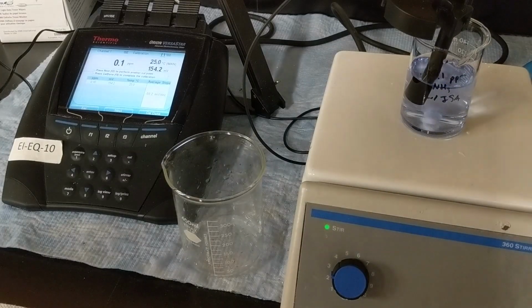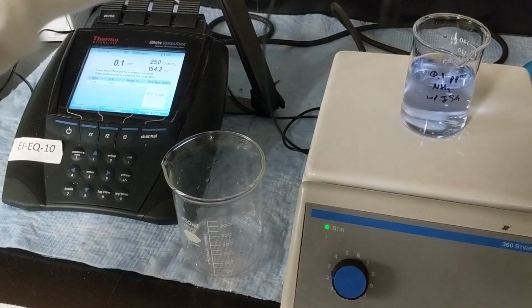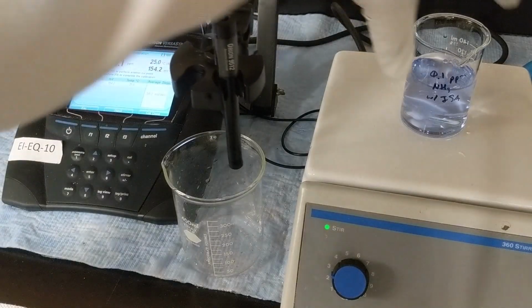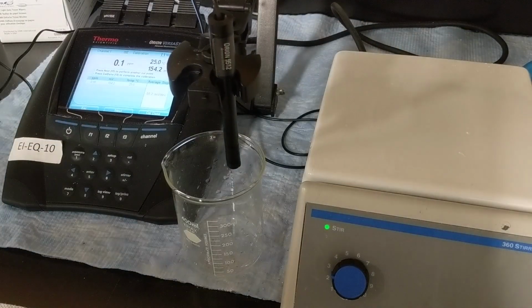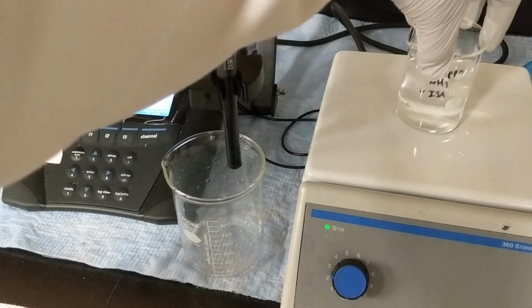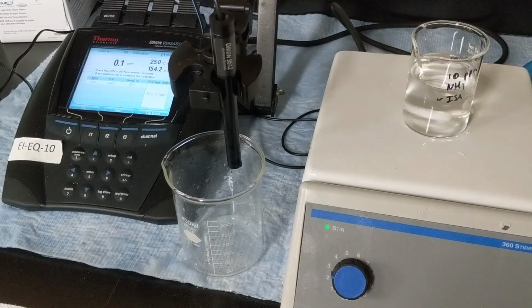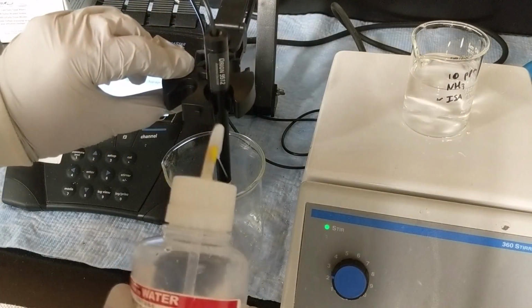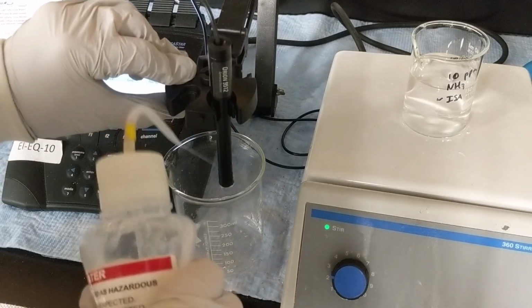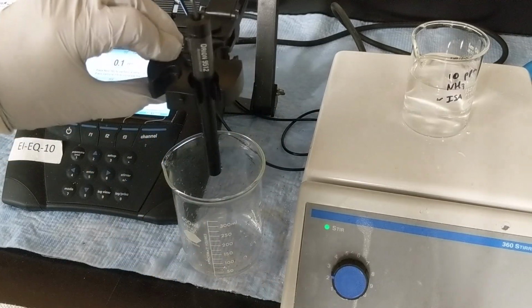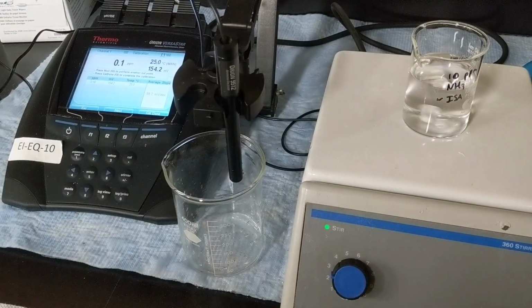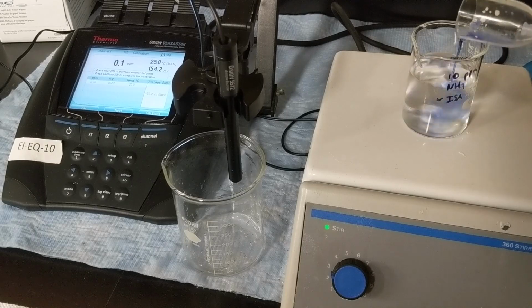We only do a 2-point calibration with our 0.1 and our 10. So I can set that aside for now. I can bring the 10 in. I'm going to rinse off my probe with deionized water. Add in my ionic strength adjuster to my 10 ppm solution.